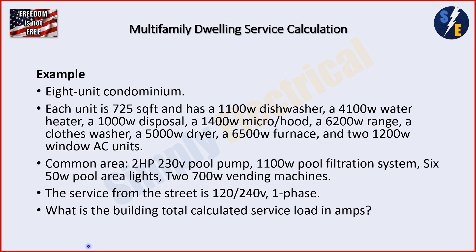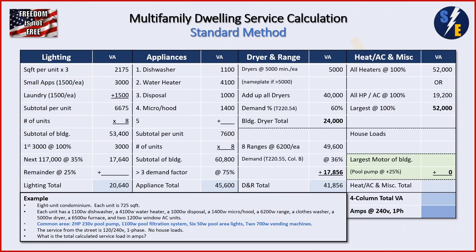Here is our example: we have an eight-unit condominium with a common area that has some house loads listed out. I'm going to start with the standard method first to show you how it works, which is really straightforward. Then we're going to go to the optional method and show you the difference between the two methods and how house loads are added. It's pretty much the same thing, but it looks a little different because they are different tables. Here's the multifamily standard method table — I won't go through it in full detail, but I do have another video on that. We get our column totals at the bottom, and in the last column we have a section called house loads, where we put our total for house loads and add it into our calculation to get our total building service.